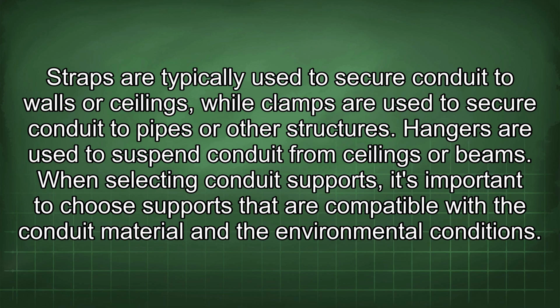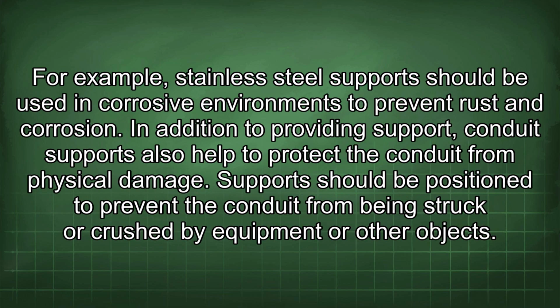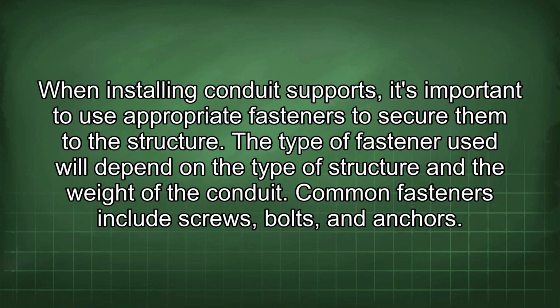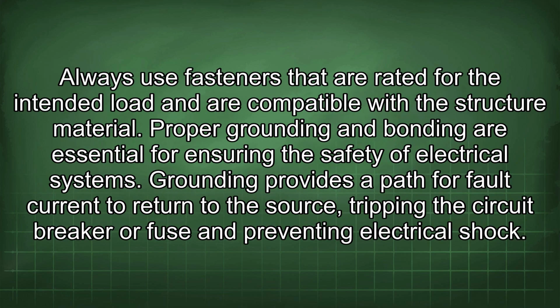When selecting conduit supports, it's important to choose supports that are compatible with the conduit material and the environmental conditions. For example, stainless steel support should be used in corrosive environments to prevent rust and corrosion. In addition to providing support, conduit supports also help to protect the conduit from physical damage. Supports should be positioned to prevent the conduit from being struck or crushed by equipment or other objects. When installing conduit supports, it's important to use appropriate fasteners to secure them to the structure. The type of fastener used will depend on the type of structure and the weight of the conduit. Common fasteners include screws, bolts, and anchors. Always use fasteners that are rated for the intended load and are compatible with the structure material.